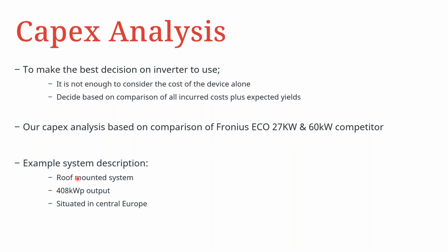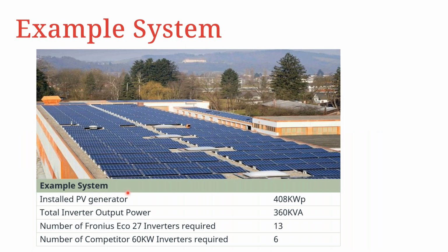So this system is a roof-mounted system with a 400 kilowatts peak output and is situated in Central Europe. This is an outlay of how the system looks in the rooftop. The installed PV modules, like earlier seen in the previous slide, is 408 kilowatts peak with a total inverter output of 360 kVA. This, of course, amounts to 113.3 inverter ratio figure.